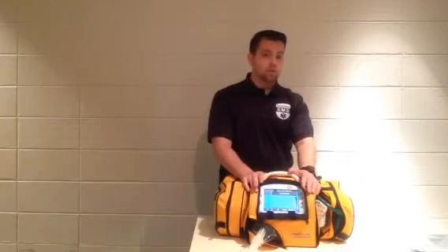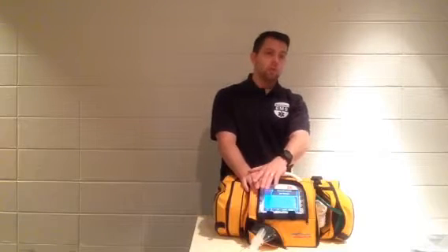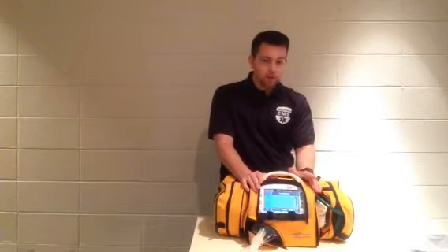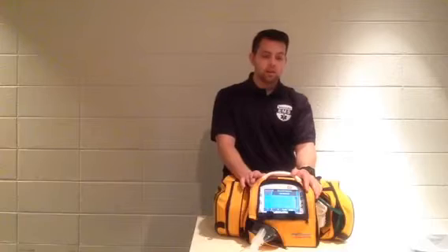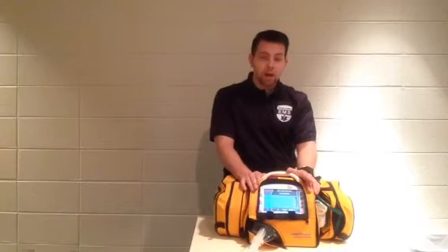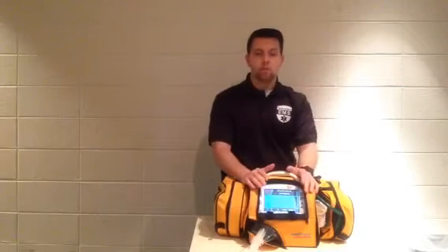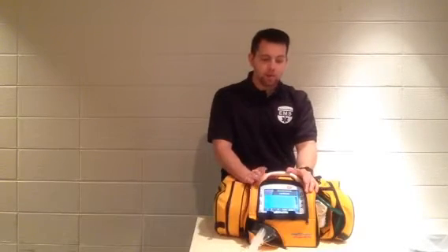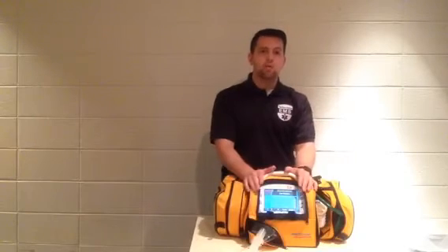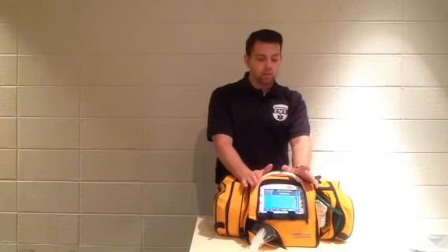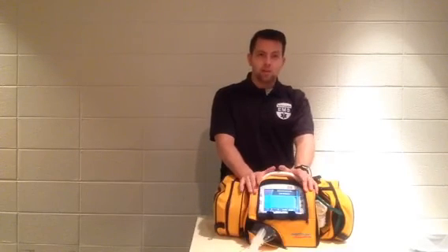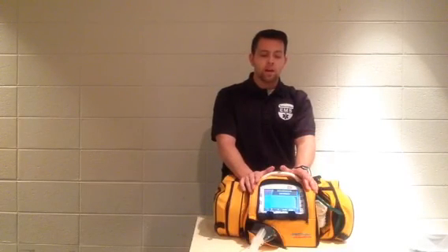That's certainly not all the features. We can change flow rate, we can change the slope, how quickly it rises to get to the amount of pressure that you want. You can pressure ventilate, you can volume ventilate. There is a CPAP option. We can set 2 different flow pressures to mimic a BiPAP type option. So this is just meant to be a general overview to get you comfortable and oriented to using this particular device.